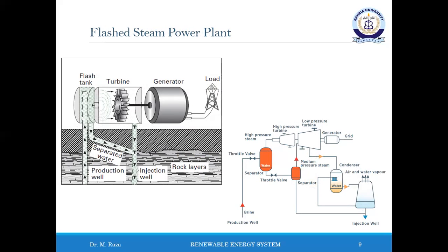Moreover, the bulk of the fluid produced, often up to 80%, remains as unflashed hot brine, which is then re-injected unless there are local direct use heating applications available. In general, therefore, a re-injection well must be available for fluid disposal at a single flash plant.